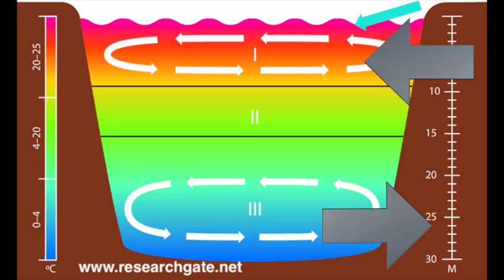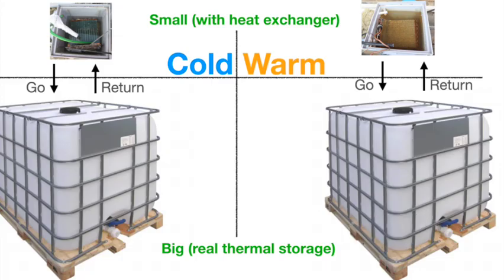By choosing the right point of discharge and extraction, of course. Discharge water from the upper side of the hot water box to the big tank and discharge it here at the surface to have maximum stratification. This will keep the bottom of the warm tank relatively cool, so that if you return the water from there to the water box with a pump, you will have a low temperature at the heat pump's condenser. It will therefore work with a better COP.